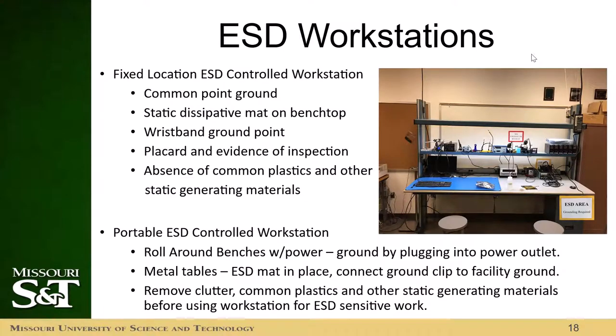More on ESD workstations: you can see in the middle there's a common ground point you can plug your wrist strap into. There's a static dissipative mat on the bench top, the ground point, and some anti-static solution visible in the picture. We'll also have a portable ESD-controlled workstation — benches where you can plug your wrist strap into the ground portion of an outlet to stay grounded. These will be metal tables with an ESD mat on top. It's also important that clutter in the lab be removed, as tripping can hurt people and damage components.